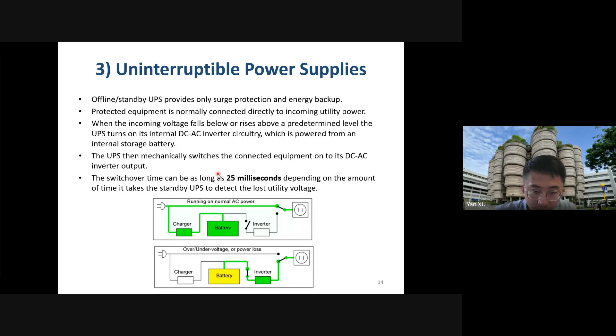Another criterion is about the capacity, the size of the UPS. In reality, the UPS batteries are in modular format. So for example, one UPS module is 6 kVA. Now depending on our load, sometimes we will use the so-called N+1 criterion in order to address the so-called single point failure. What does that mean? If we have a 12 kVA load and each UPS module is 6, sometimes exactly we only need two modules, right? 2 times 6 equals 12.